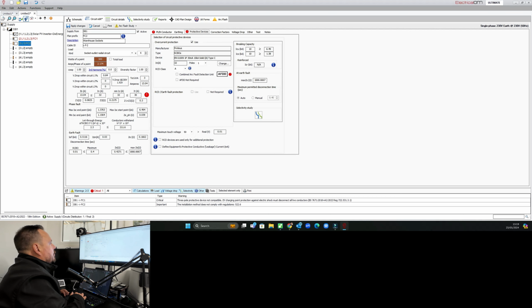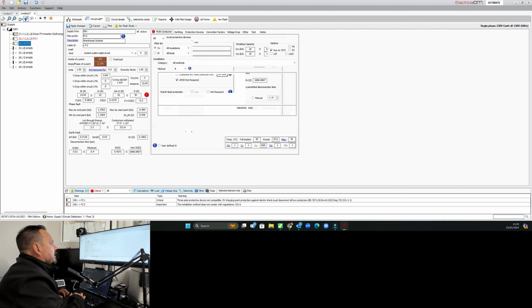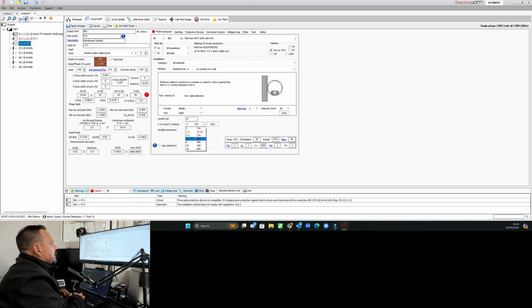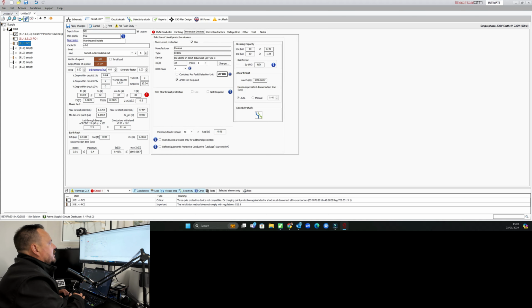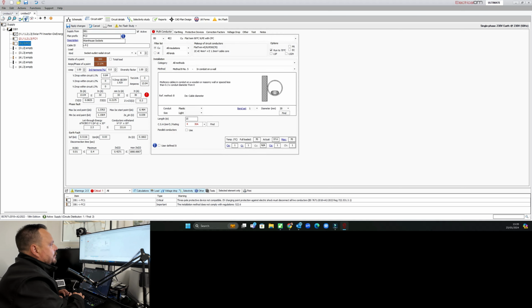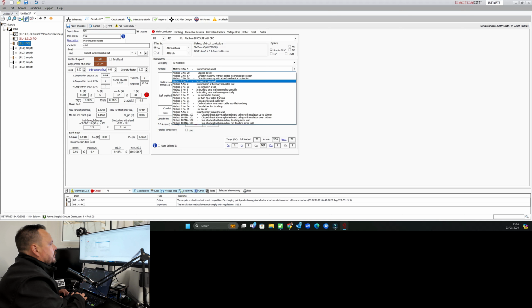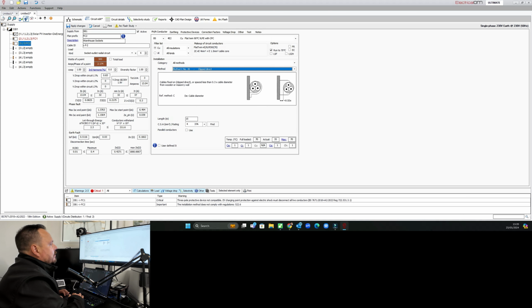So that's in there. Our protective device is now sorted, so we're going to say that AFDD is not required to clear that warning, but it is asking us to make that decision. You can see now with our sizing, because we've gone for that 32 amp breaker as a protective device, it's saying we need to upgrade our cable size. So you've got options now. We're either going to downrate the circuit, or we need to upsize our cable, and that is because of the conduit. So if we was putting this on tray, for example, if we just do that or click direct, you see the current carrying capacity of the 4mm adjusts and suddenly becomes okay.